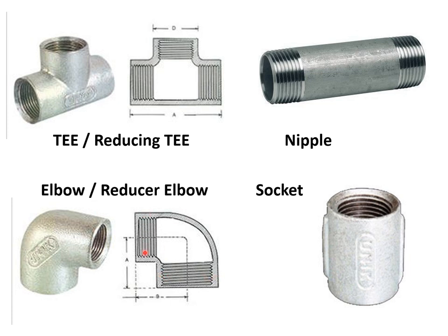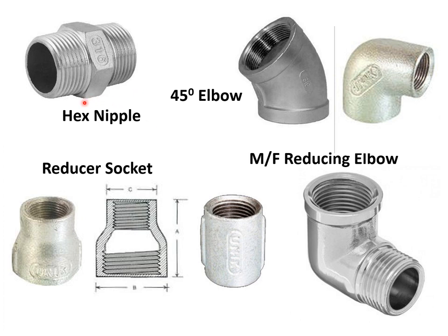The same concept applies to elbows: if both diameters are the same, then we call it a standard elbow; or if one side diameter is reduced, we call it a reducer elbow. This is the socket, which has threads at both ends on the internal side and is used to join two pipes in a linear manner. Based on its hexagonal external profile, a fitting known as a hex nipple has threads on either side. This is a 45-degree elbow, whereas earlier we saw the 90-degree or standard elbow. This is a reducer socket; a standard socket has equal diameters, but if one end has a reduced diameter, it is known as a reducer socket.